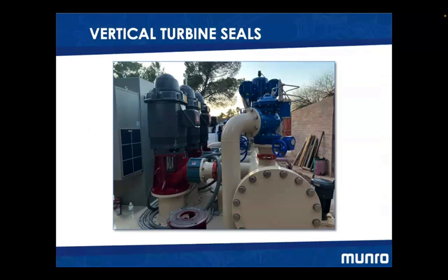Packing seals are very good at handling water that is highly turbid and has a lot of material in it that could be damaging to a mechanical seal. So maybe we might be pulling water directly out of a river. If we're pulling water directly out of the river and it didn't have an opportunity to settle itself out, we could be pulling a lot of material up into the pump that could cause damage to a mechanical seal. So we might want to select a packing style seal in an application like that.